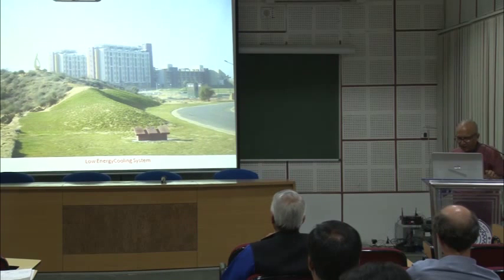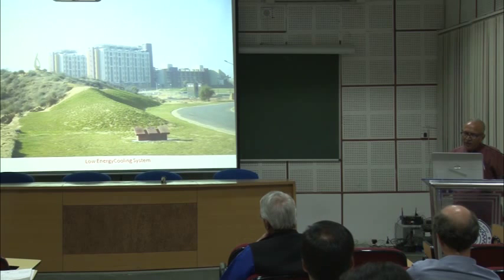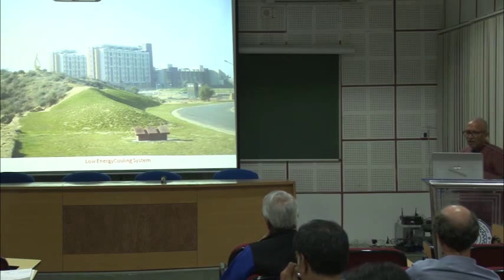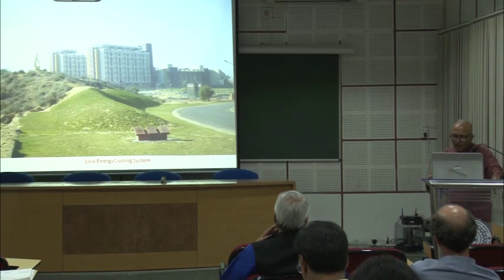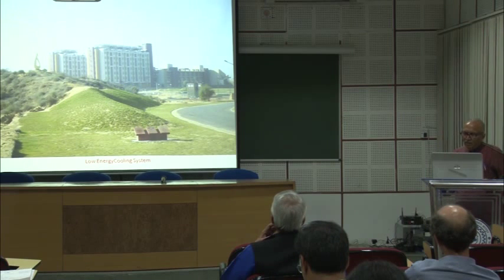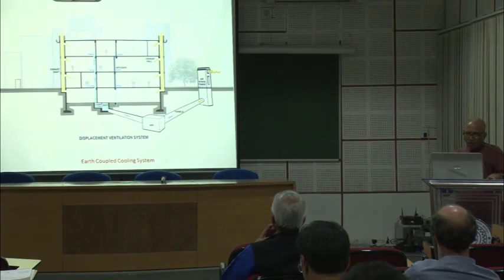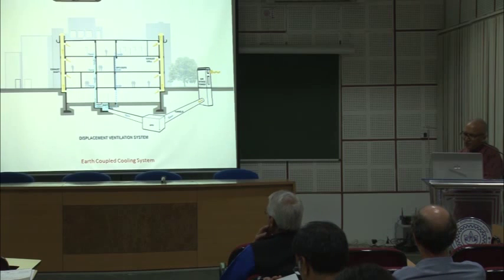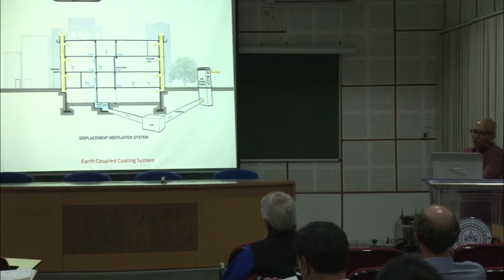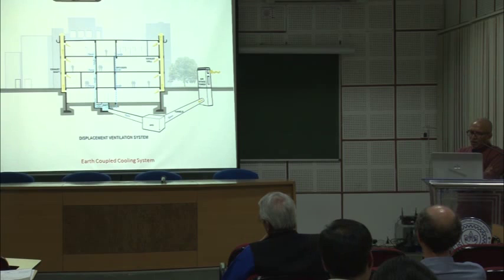Then there is, I think, the last example, or maybe one more, of a set of buildings that we did for the NIIT. This is in the desert, and one wanted a low energy cooling system, so the thermal mass of the ground itself was used as a method of cooling. Air was drawn through the ground. On the right is the air intake tower. Air is drawn through that into a tunnel about 60 meters long, and this air cools down by a few degrees, maybe 6 degrees, and then is taken further through an air handling unit, cooled down by evaporation in the dry summer months, and then supplied to the rest of the building, going out through the top.